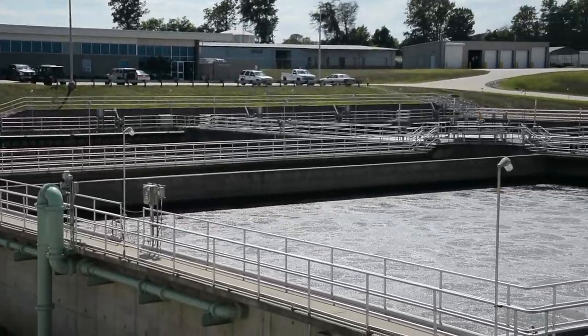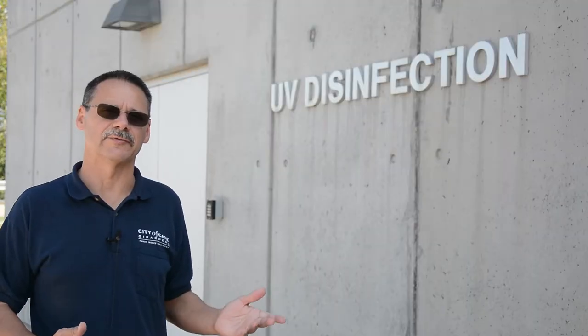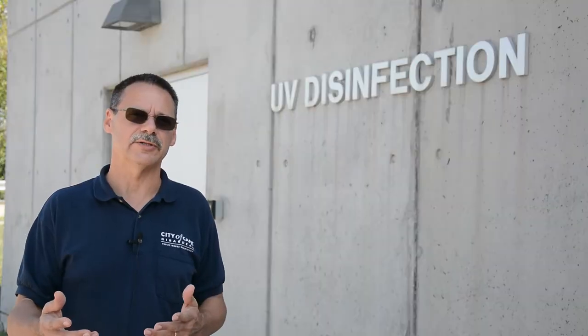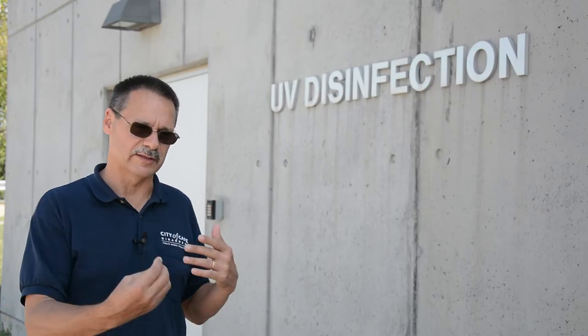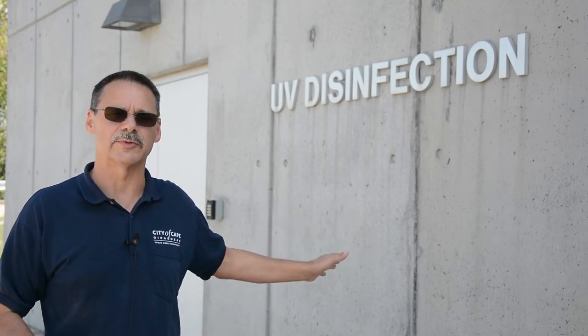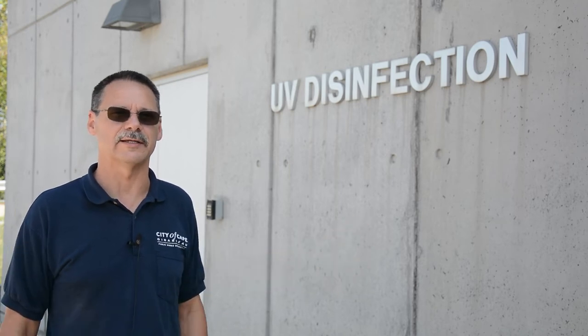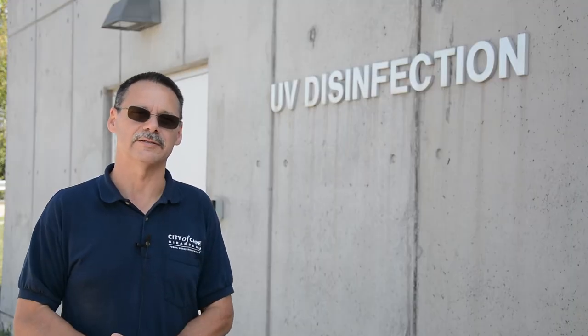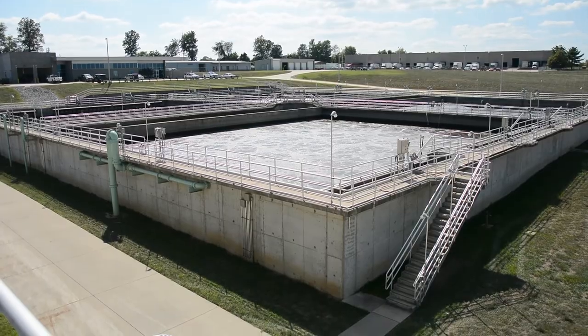As the water is being decanted from the activated sludge tanks after about two days of treatment, it undergoes one last step: ultraviolet disinfection. The water is run through a series of lights exposed to UV wavelength, and any organisms left in the water have their cell wall damaged so they cannot reproduce — they live out the rest of their life and then they're the end of their species. From there, the water is sent to the Mississippi River. Under our National Pollution Discharge Elimination System permit, this water is deemed safe to go to the Mississippi River. So if you've ever wondered where the water goes when you flush, now you know.